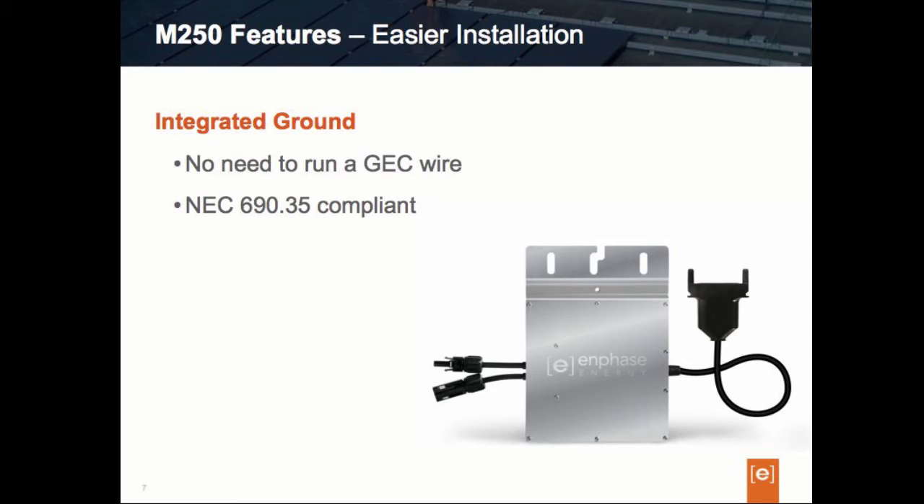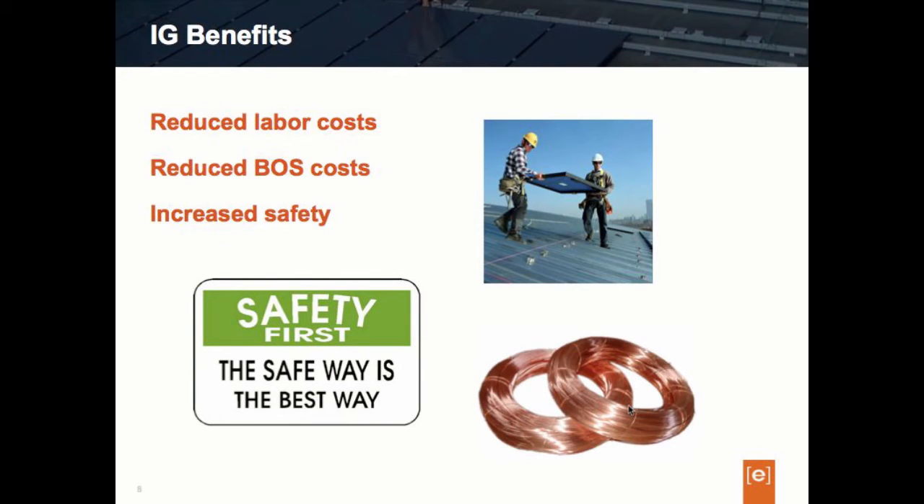The integrated ground means there is no longer a need for the DC GEC wire. The benefit is significant: without the need to run ground wire, that represents reduced labor costs for installers, as well as overall reduced balance of system costs because you don't have to pay for that copper wire. In instances where grounding washers — WEEB washers — were used, there's no longer any need to purchase or install a WEEB washer. These are all advantages of the integrated ground, along with a degree of increased safety overall in its electronics.